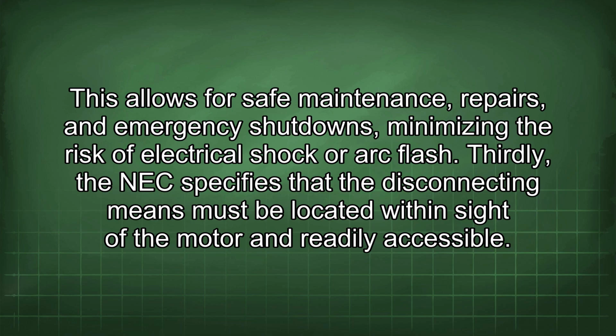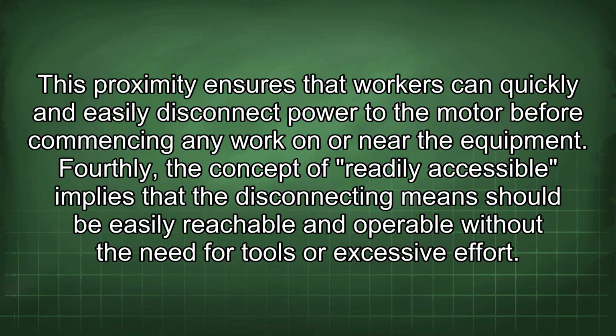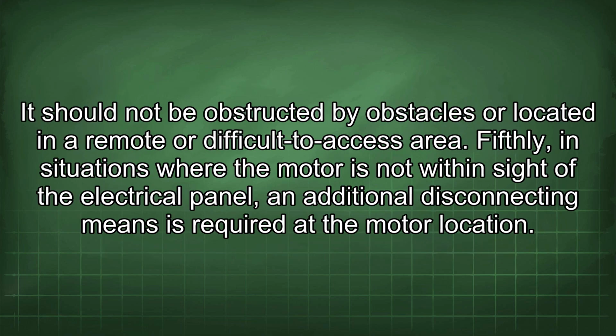Thirdly, the NEC specifies that the disconnecting means must be located within sight of the motor and readily accessible. This proximity ensures that workers can quickly and easily disconnect power to the motor before commencing any work on or near the equipment. Fourthly, the concept of readily accessible implies that the disconnecting means should be easily reachable and operable without the need for tools or excessive effort. It should not be obstructed by obstacles or located in a remote or difficult to access area.